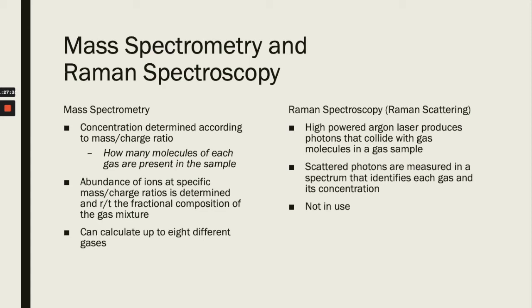The mass spectrometer basically allows the identification and quantification on a breath by breath basis of up to 8 different gases. It can identify oxygen, nitrogen, nitrous, halothane, enflurane, and isoflurane. And it also can identify helium, CO2, argon, and desflurane as well.